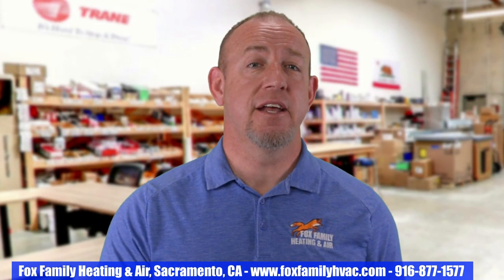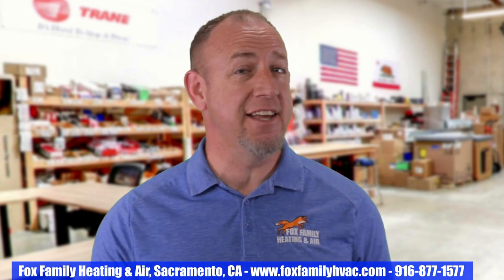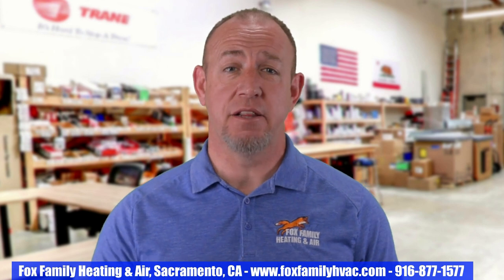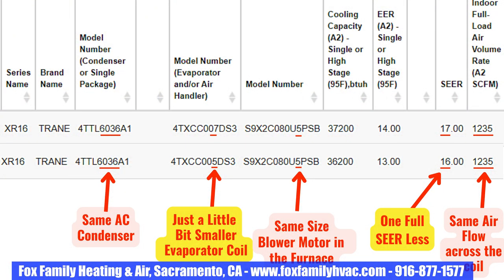Let's look at a SEER rating on AHRI directory for a Trane split system where the AC condenser is located on the side of the house and the furnace is located in the garage, closet, or attic. In the example, we have the same 4TTL6036A1 condenser, and in the model number nomenclature, the first 6 in 6036 means 16 SEER. The 36 stands for 36,000 BTU capacity, a 3-ton system.